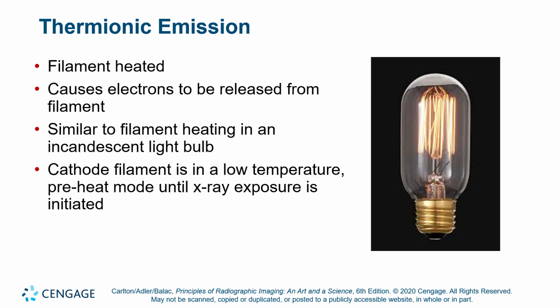And so there's usually a lag between preparation and boost. If you mash it all down at once, you're going to experience that lag. It's about 1.5 seconds. The circuit is allowing time for the filament to heat up, so we have an available electron cloud, but also for the rotating anode to get up to speed. We need that thing at about 3,000 RPMs or faster, okay, in order for it effectively to distribute the heat from the bombardment of the electrons.